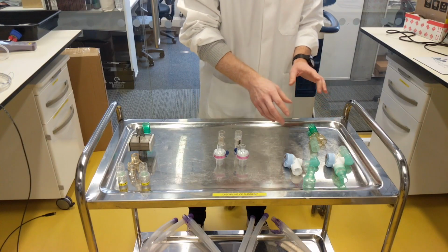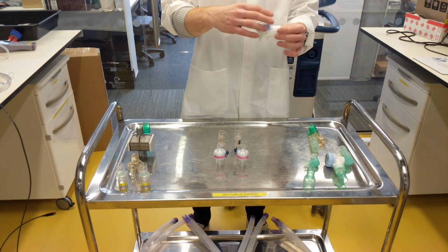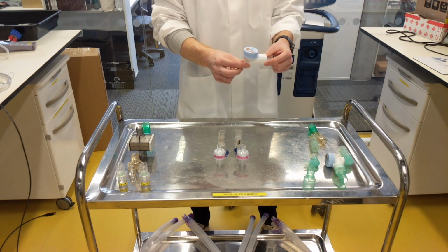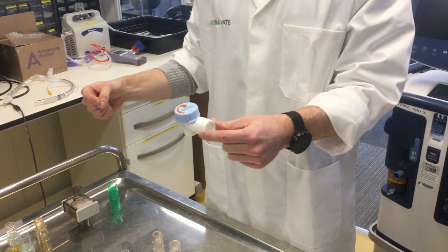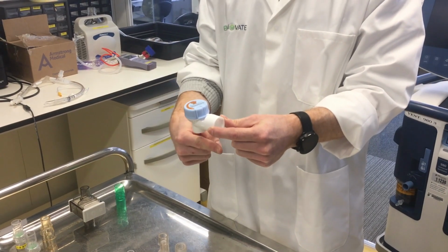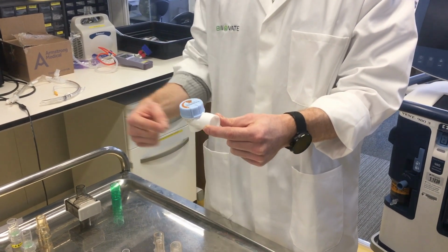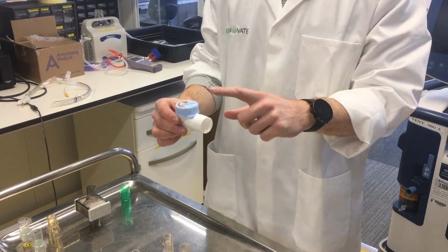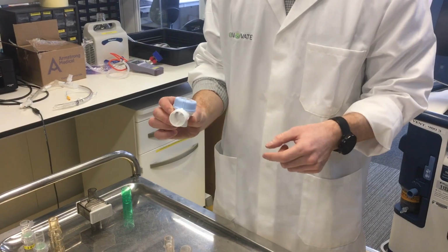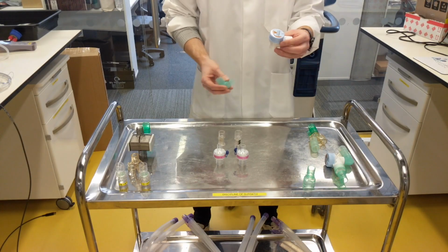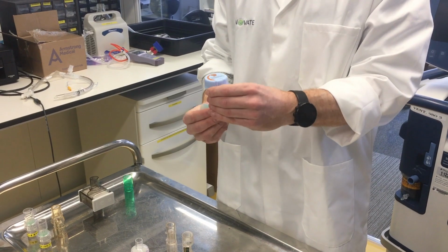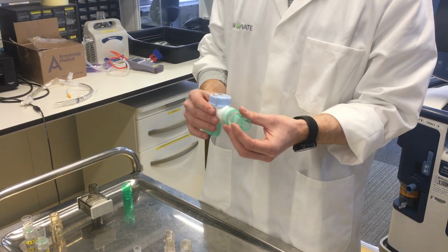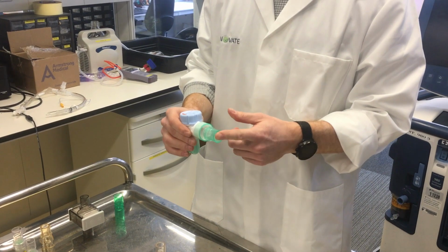Following that, then we have our APL valve set up. How we're using this APL valve is slightly different to its standard use. Typically it would be on top of a C circuit in a T configuration with the flow going this way, and then any excess pressure just being vented to the atmosphere through this large port here. How we're using this slightly differently is to run all the flow through the bottom using this elbow, and then we're using a step down connector on the exhaust to route into the inspiratory limb.